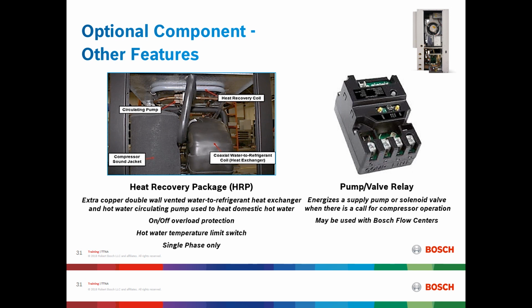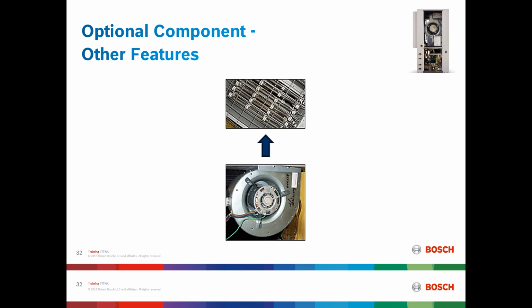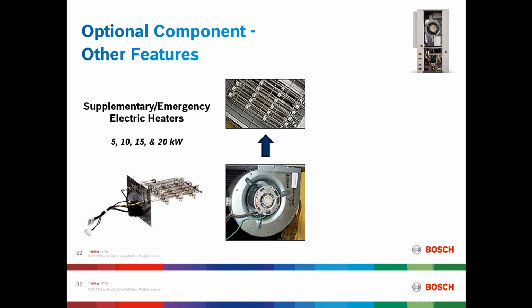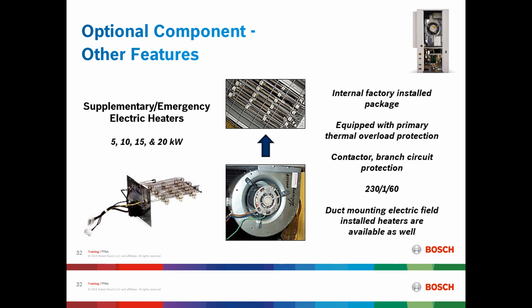The SM Rev V can have a pump valve relay, which energizes a supply pump or a solenoid valve when there is a call for compressor operation. This device may be used with Bosch flow centers for a geothermal application. The last optional feature would be electric heaters used for supplementary or emergency heat. We offer 5, 10, 15, and 20 kW heater sizes. These heaters are internal factory installed packages. They are equipped with primary thermal overload protection, contactor and branch circuit protection, available only in 230 volt single phase 60 Hz power. If they do not meet the needs, we also have duct mounting electrical field installed heaters available as well.